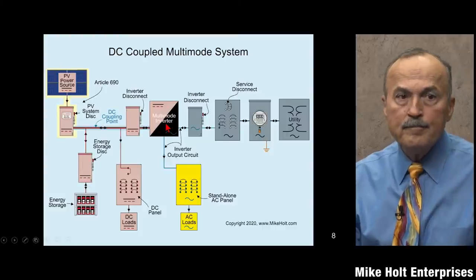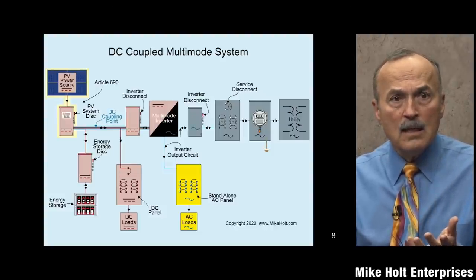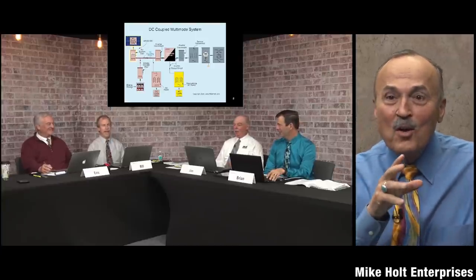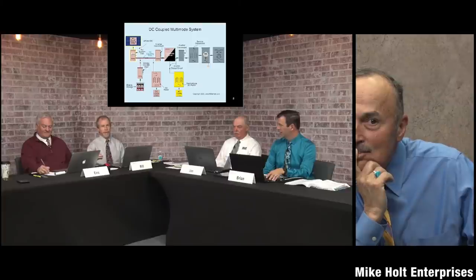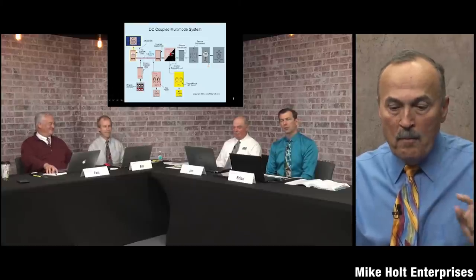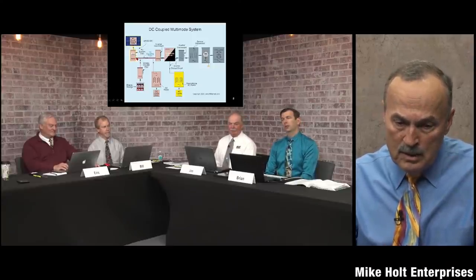Electrons go from both the PV source and the battery through the inverter disconnect and into a multi-mode inverter. A multi-mode inverter is different from an interactive inverter - by definition, it has more than one mode. One mode is interactive and the other is standalone. The term 'standalone' is used because people understand it; 'island mode' is the newer code term but 'standalone' is the street-level terminology.